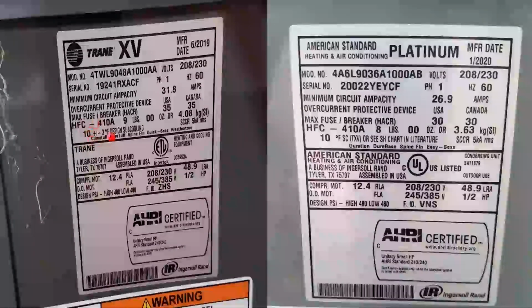This one says plus or minus 3 degrees, so it's 10. So it could be up to 13, and down to 7 degree subcooling. So keep that in mind. They are going back to the plus or minus 3 degrees, but usually our target window is 10 degree subcool. So always refer to your data plate or your desired subcooling.